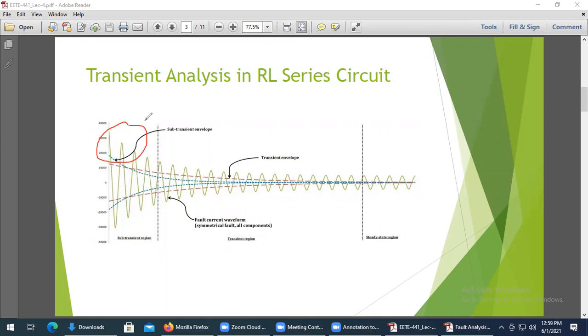So this is known as the subtransient periodic current. This high magnitude current that occurs at the very beginning of the fault is classified as subtransient fault current. Have you heard this name before? No, sir. Okay, so this is called subtransient fault current.